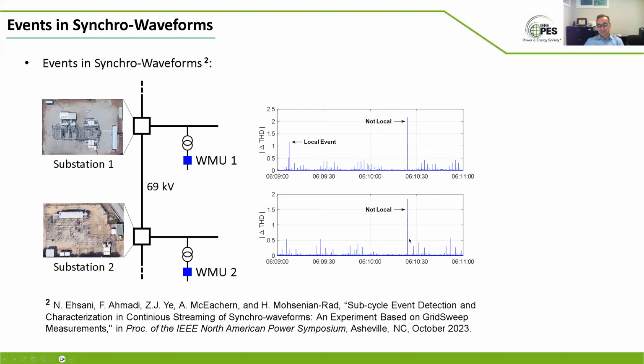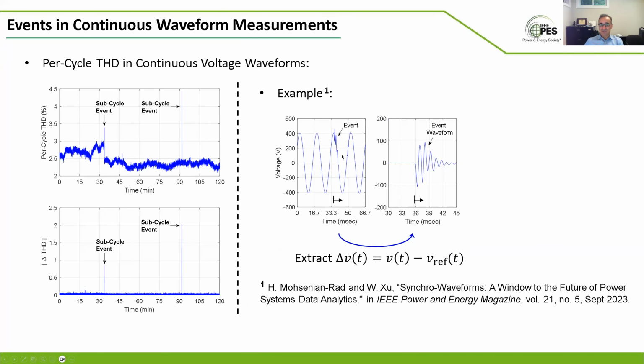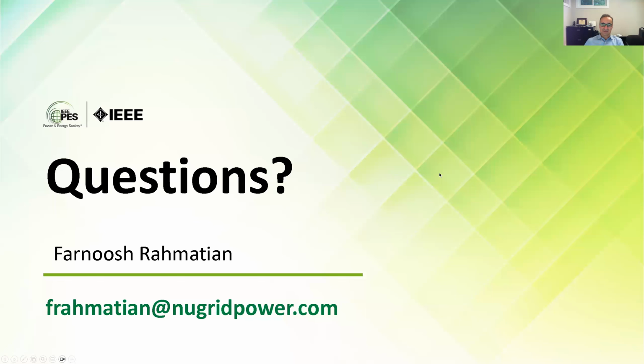But you see something happen here in terms of signal distortion that you see at both locations at the exact same time and somewhat similar in terms of orders of magnitude. Say, this is not local, that's a sort of grid event issue or something that is common between the 2 sites. That allows for a lot more root cause analysis and event analysis if something happens, especially if, in addition to total harmonic distortion, you capture the wavelets and waveforms and see what similarities they have. I stopped there. Again, as I said, this whole thing is fairly early in its introduction. The traveling wave was a neat, simple use case. The same type of measurement can allow you to go after grid analysis, transformer analysis, all sorts of events when you have that higher resolution and synchronized information.